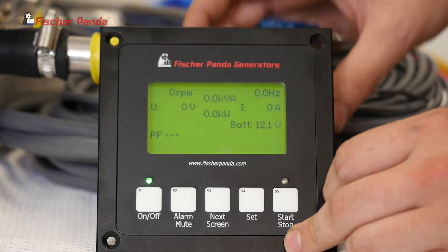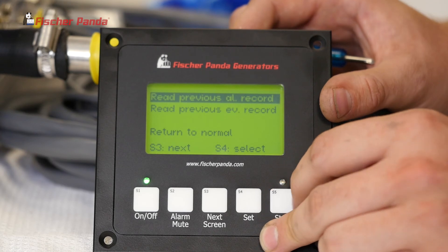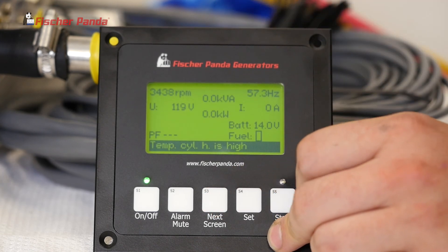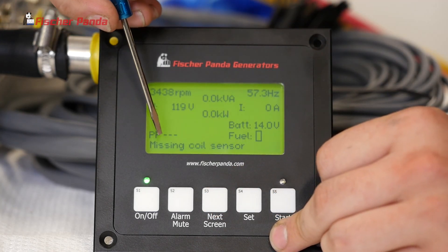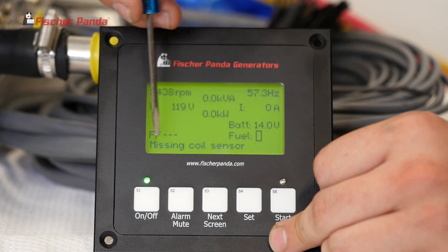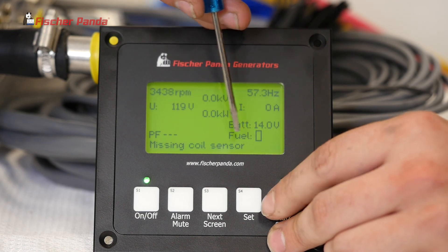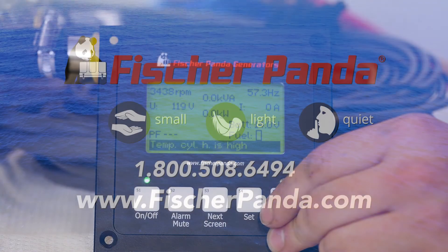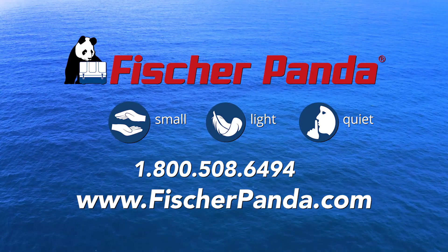Now you're back at your start screen. When reading your alarm history, select the alarm with S4, then press S3 to view it. It's important to note: the message with the black background is the reason the generator shut off. The other messages are auxiliary — things that were also occurring at the same time. The cause of the shutdown always has the black background. For more information and further assistance, contact your local Fischer Panda dealer or our service department.